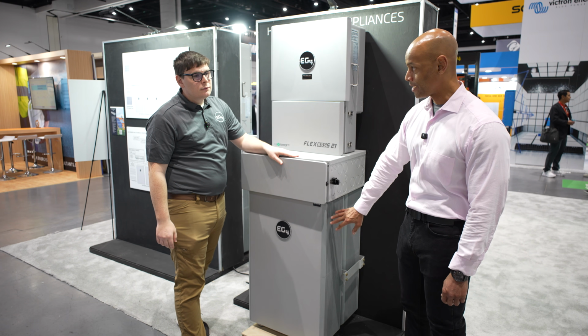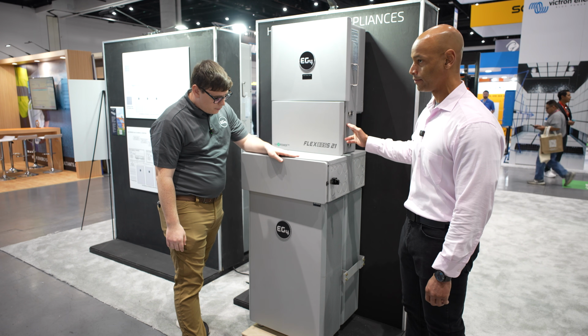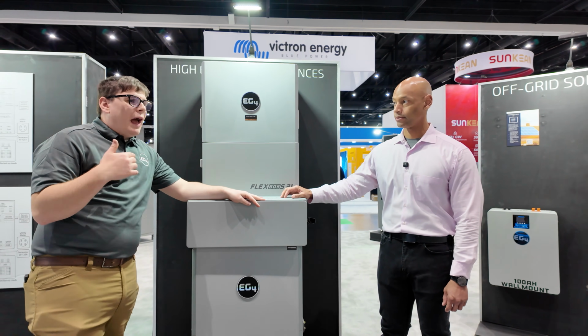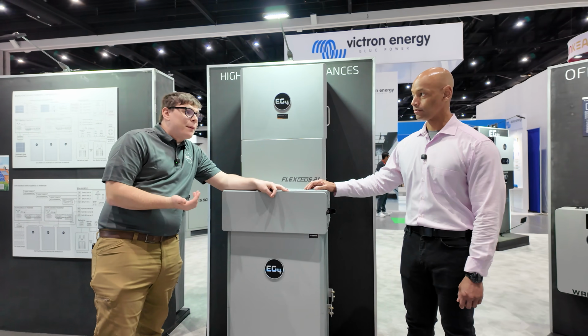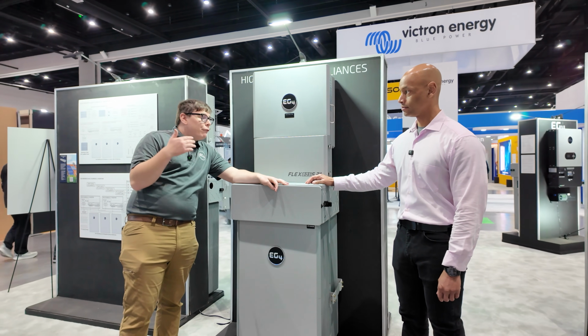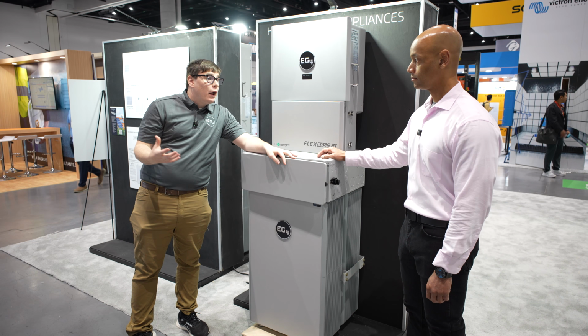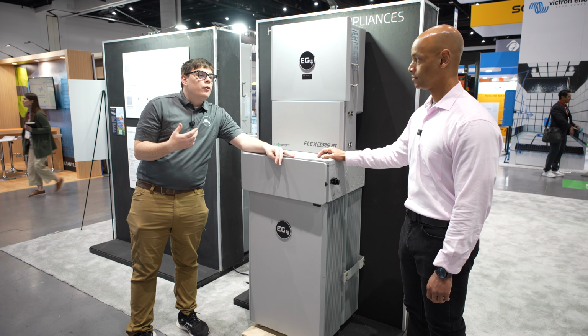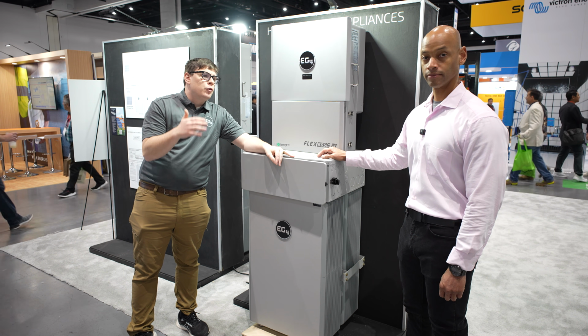James, is there a limit to how many Power Pro batteries you can connect to a single inverter? Well, we've had people do 64 batteries in a system, but after about 5 batteries, after the 75 kilowatt hour range on a single inverter, you have to use a busing system.